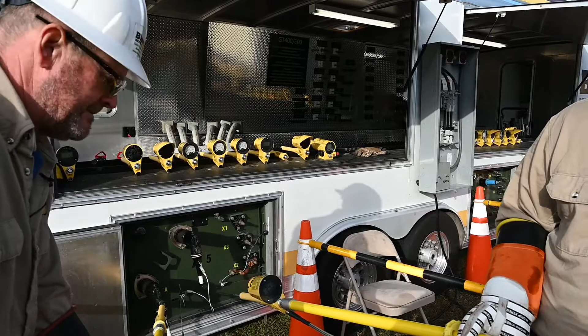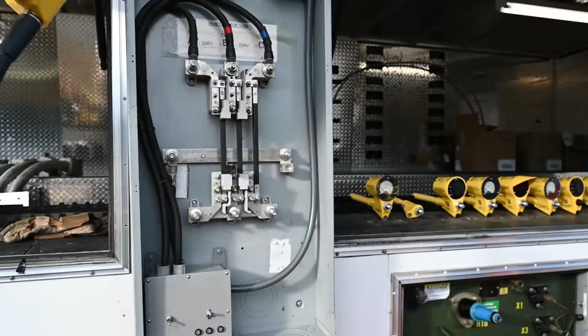This tool, accurate, starts working at 1 volt, so we can use it to phase the secondary panel. Here we'll go phase to ground first. It's a 120/208 panel. We see 120 volts. We'll go phase to phase. Looks like in phase, so we see 0 volts. Here we're out of phase, so we see 212 volts. And this tool also goes up to 25 kV.